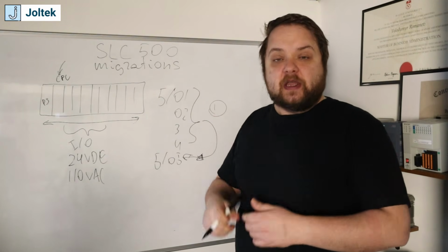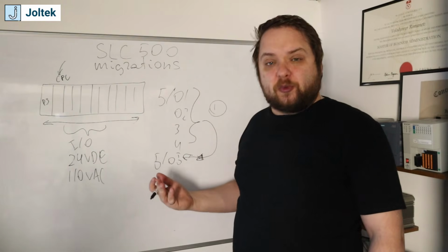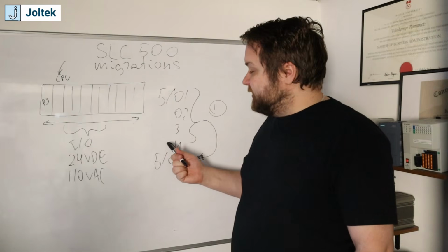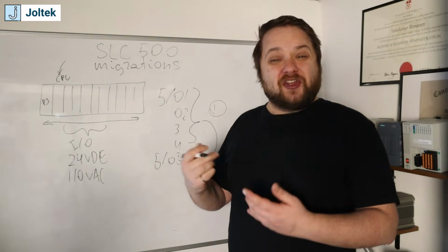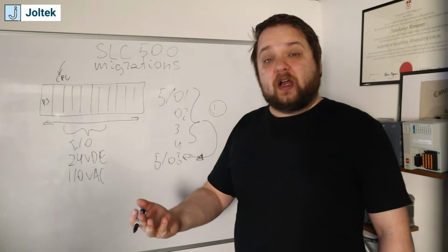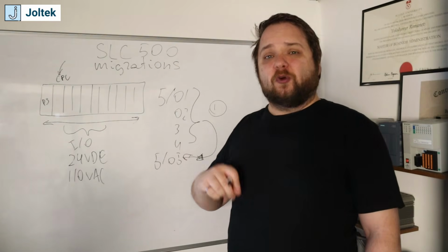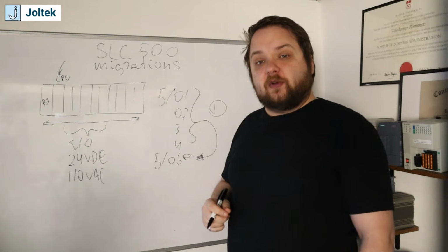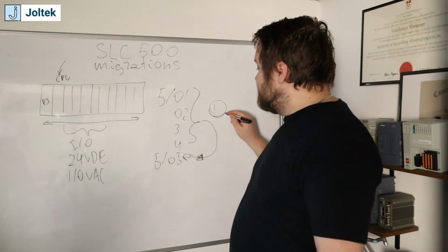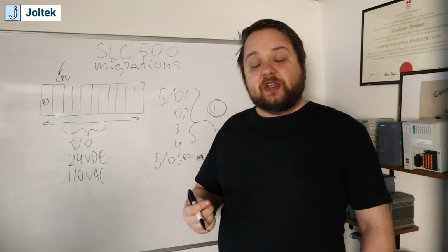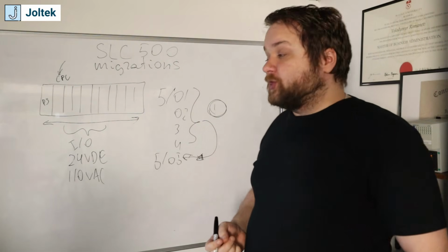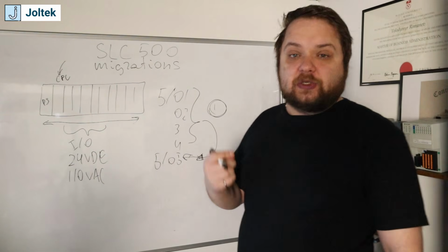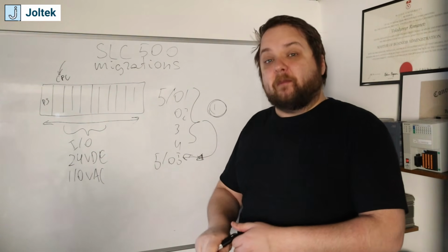You don't necessarily need that much downtime. You simply move the program over from whichever PLC. Of course, ensure that the PLC is not using some kind of a converter from, for example, Data Highway Plus or RS-485 or RS-232 from the main connection in front of the PLC. So once you have done this migration, as I have mentioned, you can take the time to understand what the program actually does and what is possible for you in terms of a more permanent migration.